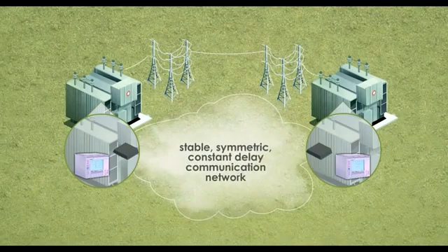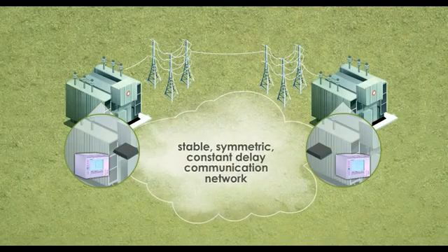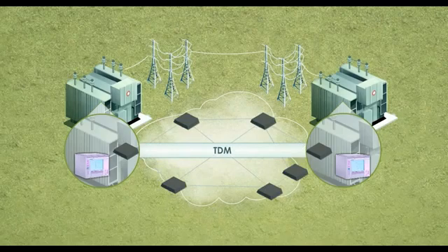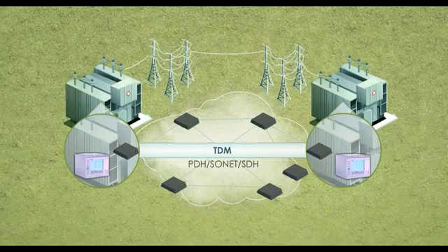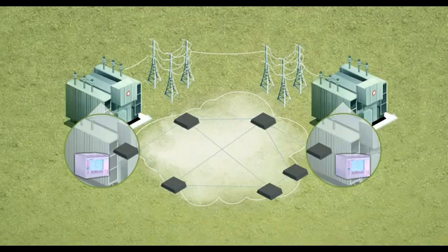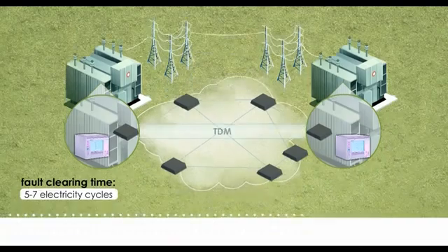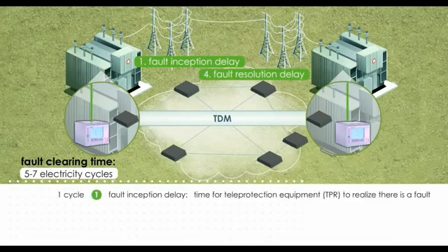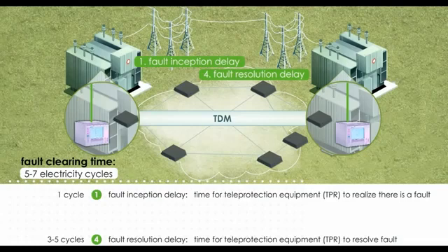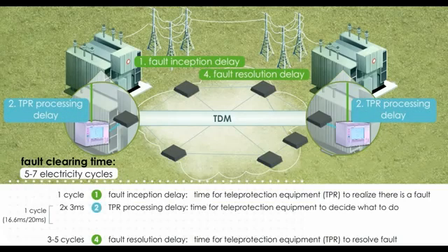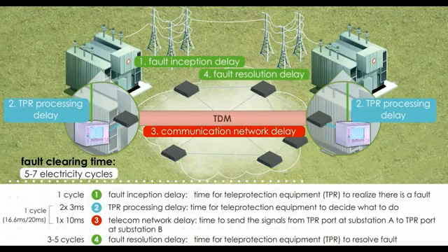Teleprotection relays rely on a stable, symmetric, constant delay communication network for providing a communication channel between them. Traditional communication networking utilizes TDM transmission architectures based on PDH Sonet SDH to provide the communication channel between relays. Today's teleprotection applications are typically developed using a total fault clearing time of five to seven electricity cycles. The fault inception and fault resolution delay take between one and three to five cycles respectively. This leaves one cycle — 16.6 milliseconds in a 60 Hz grid or 20 milliseconds in a 50 Hz grid — for total end-to-end delay comprised of teleprotection equipment delay and communication network delay, typically leaving approximately 10 milliseconds for an acceptable total communication network delay.